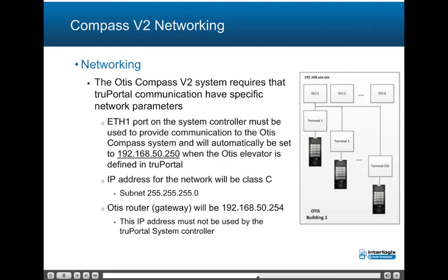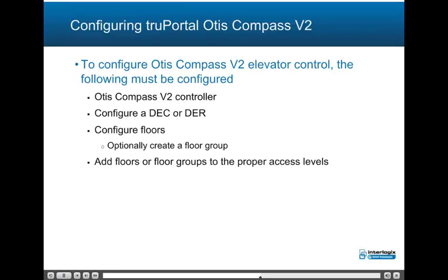ETH1, the second port on the system controller, must be used to provide communication to the Otis Compass system, and it will automatically be set to 192.168.50.250 when the Otis Elevator is defined in TruePortal. The IP address for the network will be class C using a mask of 255.255.255.0. On the Otis system, the Otis router or gateway will be 192.168.50.254; this IP address must not be used by the TruePortal system controller on ETH0. To configure Otis Compass V2 elevator control, configure the Otis Compass V2 controller, configure a DEC or DER, configure floors and optionally create a floor group, then add floors or floor groups to the proper access levels.